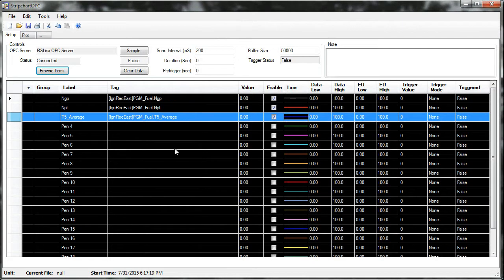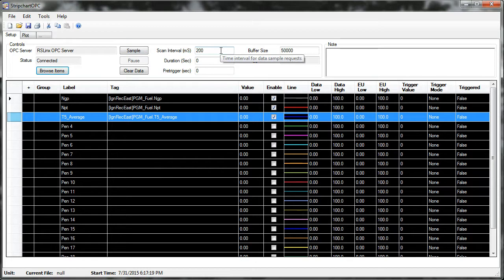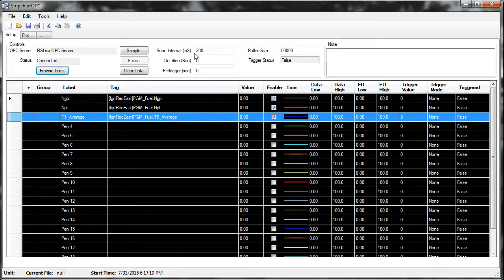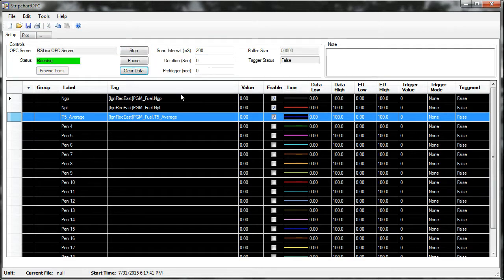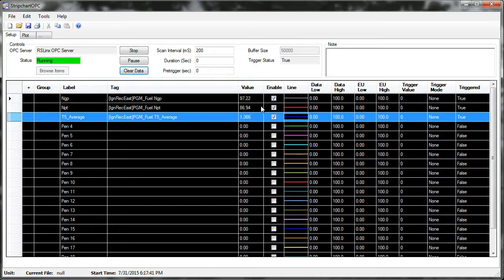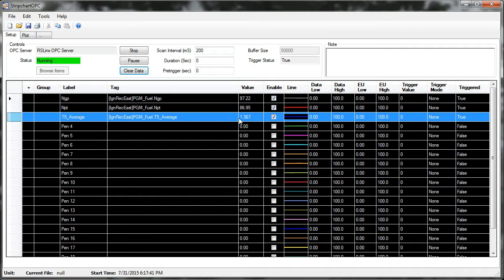So now I can scan in real time, and my interval is set for 200 milliseconds. You can scan maybe as quickly as 20 milliseconds, depending on the bandwidth of your connection to the PLC. So now I'm attempting to read the data from the unit, and there it is, coming in live. NGP, NPT, and T5 average.